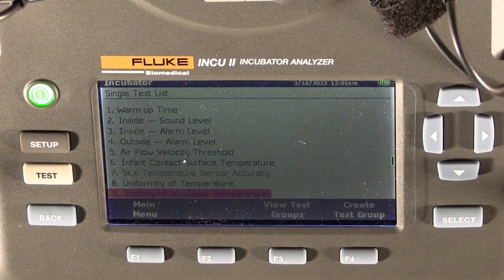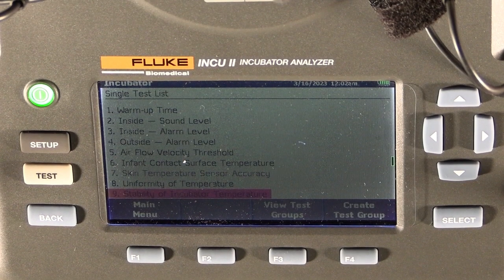Stability of incubator temperature, number 9. During this test, we want to make sure that once the temperature has reached its stable temperature, it will stay at that temperature, that it will not fluctuate up and down, that we maintain a constant temperature.